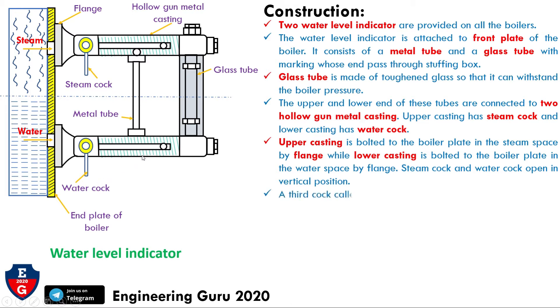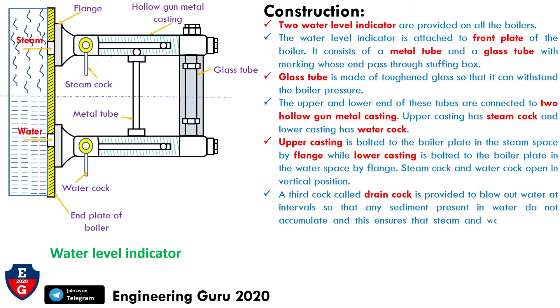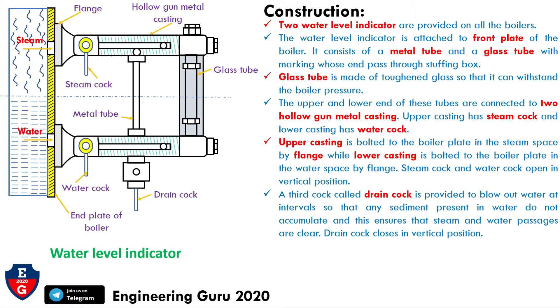A third cock called the drain cock is provided to blow out water at intervals so that any sediments present in the water do not accumulate. This ensures that the steam and water passages are clear. The drain cock closes in the vertical position — this is different from the other two cocks. The drain cock is mainly used to keep the steam and water passages clear.